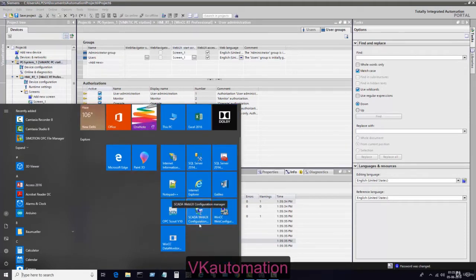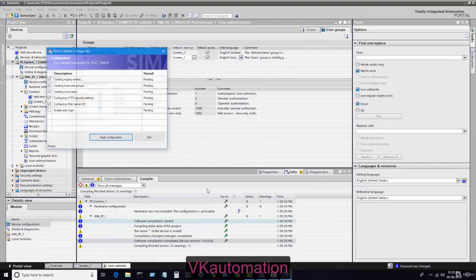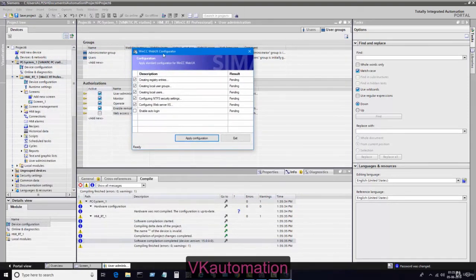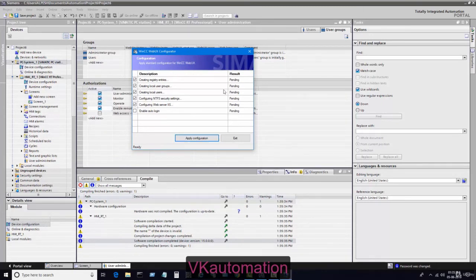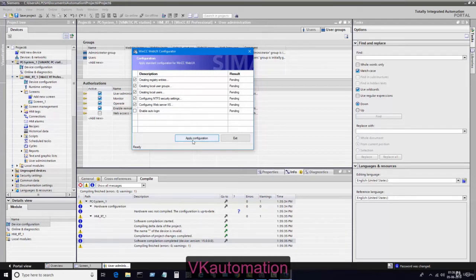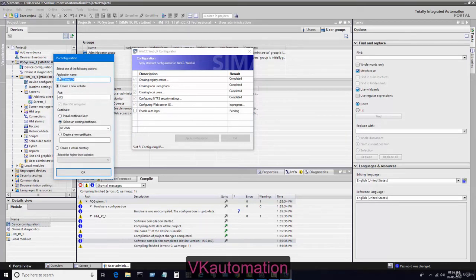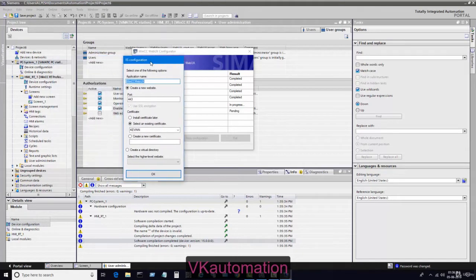I will go to my start screen and click SCADA Web UX configuration. When you open SCADA Web UX configuration, this screen will appear. You have to tick all this and untick enable auto login, then apply the configuration. This type of IIS Internet Information Services menu will open.